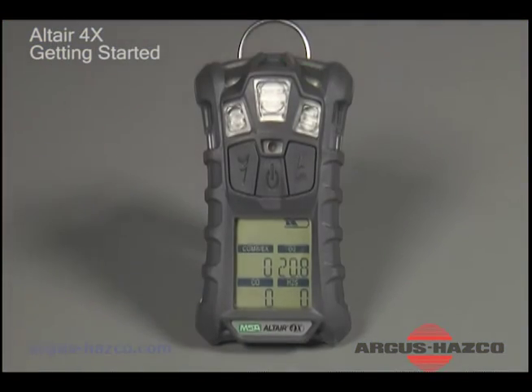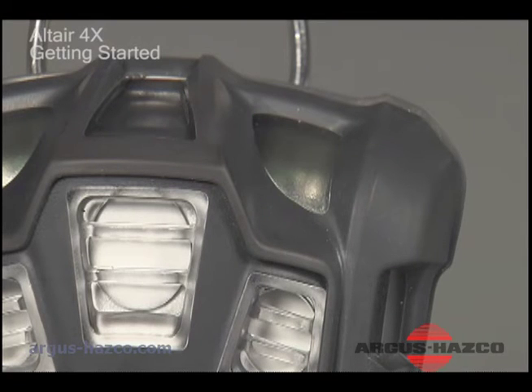When in measure mode and enabled, MSA's Green Safe LED feature flashes every 15 seconds when all of the following conditions are met: all installed sensors are reading fresh air values, STEL and TWA values for CO and H2S are set to zero ppm, and the instrument has sufficient battery charge remaining.